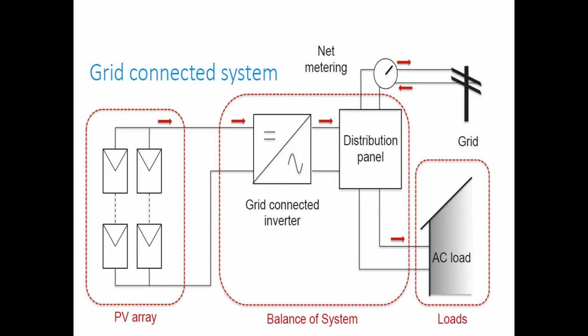So when installing a PV power plant, the inspectorate checks whether all these requirements are met, like whether the system isolates when supply turns off, and what the injection of power or THD is. THD is the level of harmonics we measure, and there's a standard it should be below. They check all these requirements, and only after checking is the plant allowed to connect to the grid.